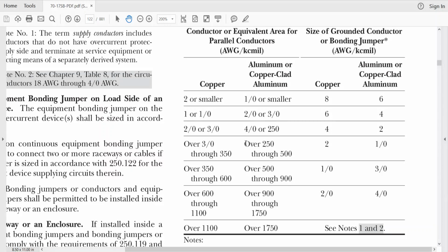Well, some people make the mistake and go here, and that says over 250. Don't make that mistake. You go right here. So it's the 4/0 or 250 size of the conductors. You're going to need either a 4 copper or a 2 aluminum. So that's your choices here. It would either be a 4 copper or it would be a 2 aluminum.